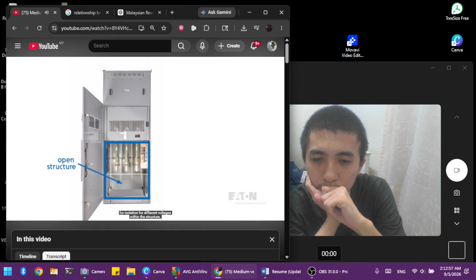Inside, the structure is open. Barriers and compartmentalization are not required, as they would be in other designs, and there's no requirement for isolation for different voltages within the structure. Switching and protective devices are typically fixed-mounted, and bare bus is the standard, with no insulation in place.